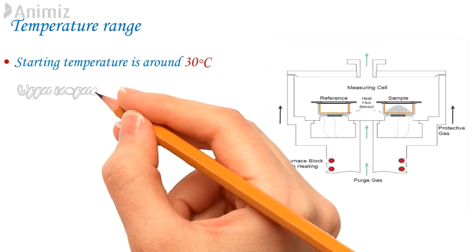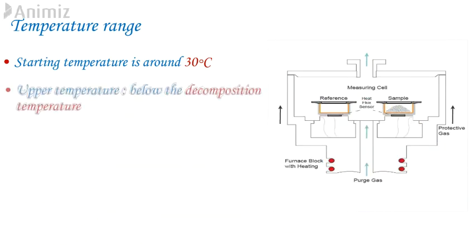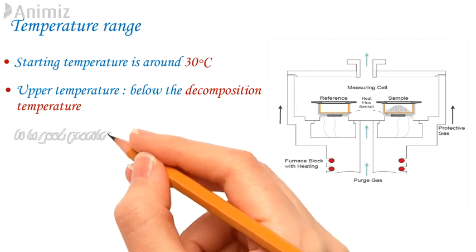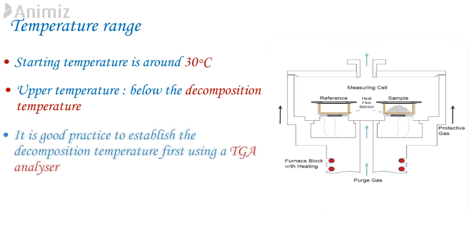10. Temperature Range. The starting temperature should be well below the beginning of first transition that you want to measure in order to see it clearly following a period of flat baseline. This should take into account the period of initial transition where the scan rate is not yet fully controlled and baseline is not stable. With ambient DSC systems the starting temperature is often around 30 degrees Celsius. The upper temperature should be below the decomposition temperature of the sample. Decomposing a material in DSC normally gives rise to very noisy drifting response and evolved volatiles will contaminate the system. It is best practice to establish decomposition temperature first before using DSC analyzer.